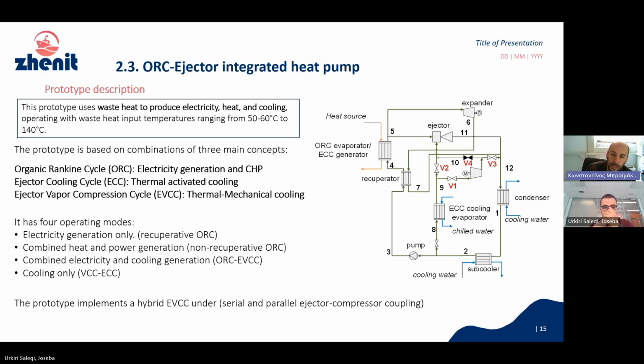And what has been implemented in our prototype is a variation of the ejector cooling cycle that also combines a vapor compression cycle. So we have a hybrid, thermally activated and mechanically driven chiller that is called the ejector vapor compression cycle, or EVCC, according to the terminology that we use. So in total, we have 4 different operating modes because of all these technologies that are coupled together. First of all, we have the electricity generation mode. In this case, we only generate electricity. And what we have is a standard ORC with a recuperator.